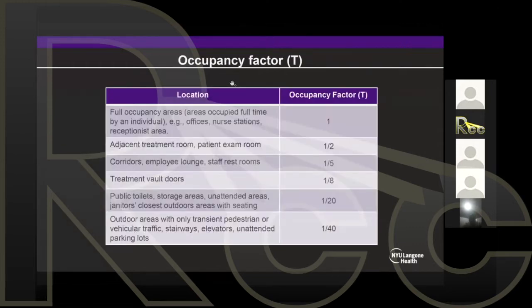Occupancy factor, right? This factor accounts for the people behind that barrier. This table is right out of NCRP 151. When you have something like an office, or a control room for a Linac, you know that area is always occupied by the same individual or individuals, so the occupancy factor is basically 1. Then you have other areas where you don't expect the same person to be there for the 40-hour week, like an adjacent treatment room or a patient exam room. It might be the same people, like the therapist or the physician, going into a room, but they're not going to be there for the full time. So these get reduced to 1/2. And then you can see the rest in the table.